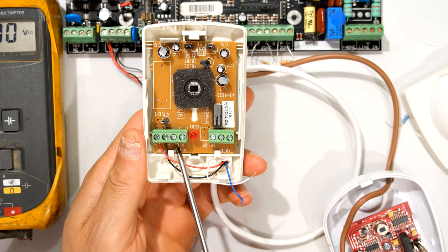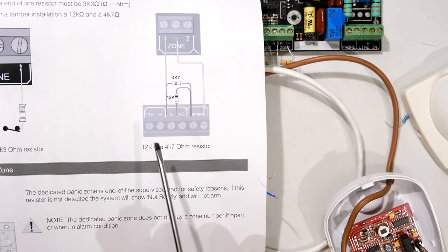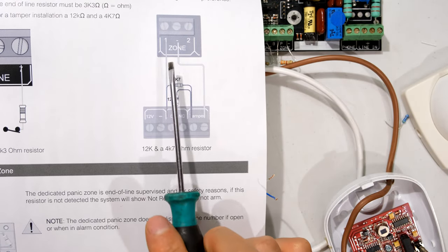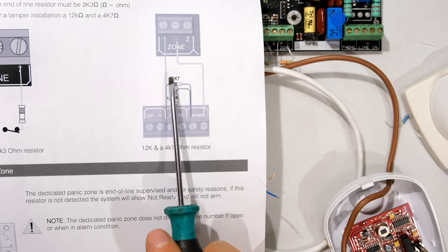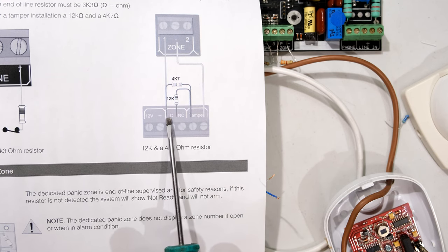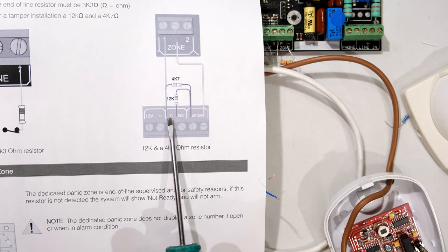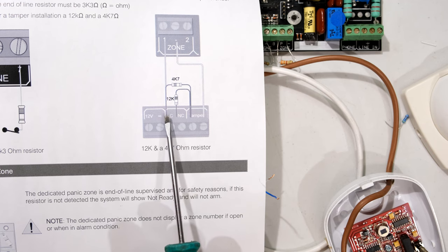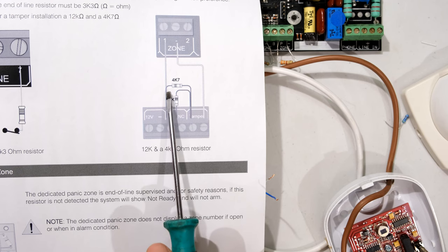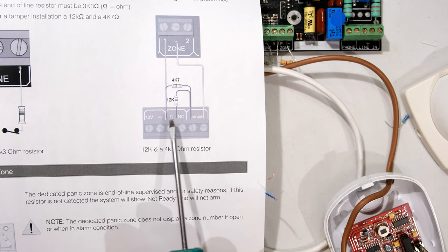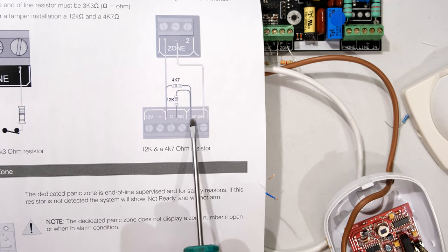Now the next terminals are the normally closed terminals. Having a look here you can see that from the zone the positive is going straight into the first connector of the normally closed terminal and also notice that there's a 4k7 resistor that links this terminal to the first wire of the tamper.